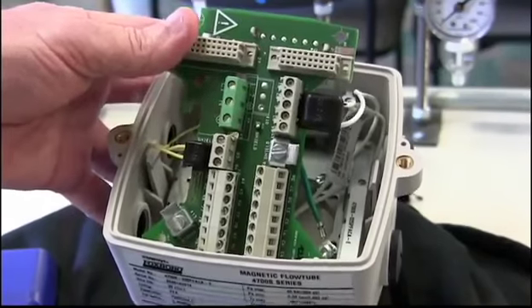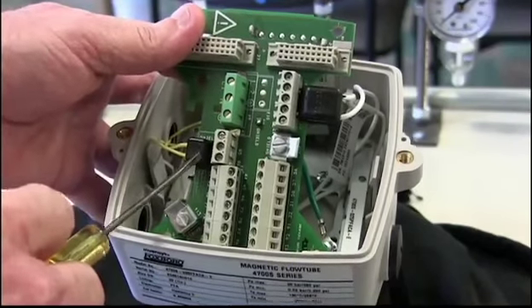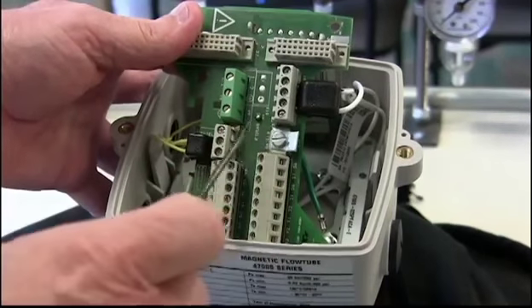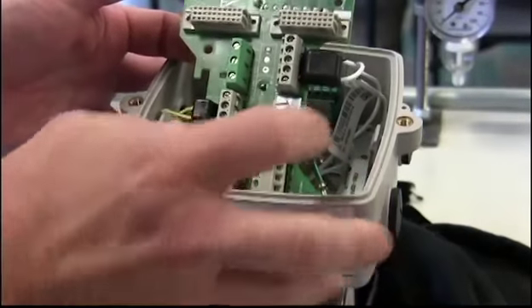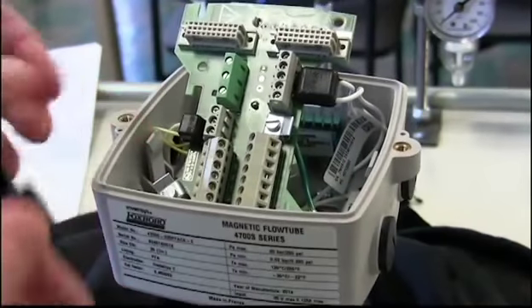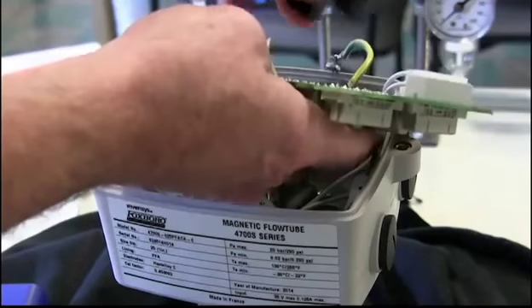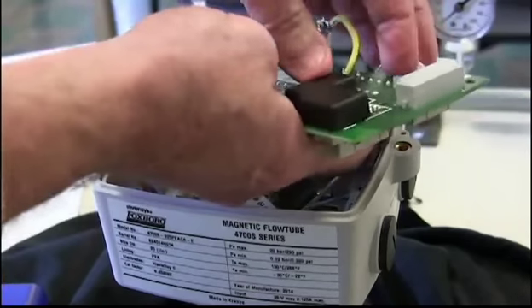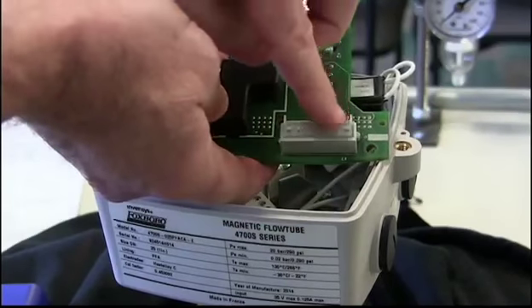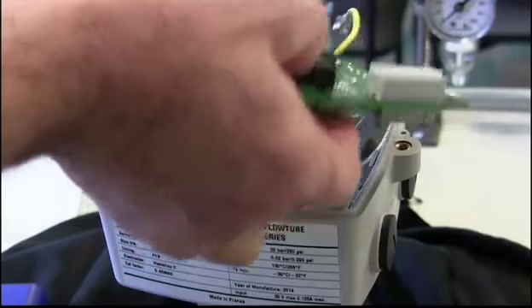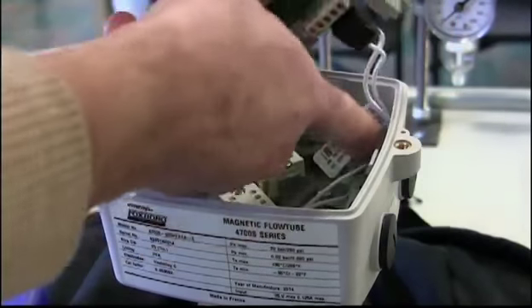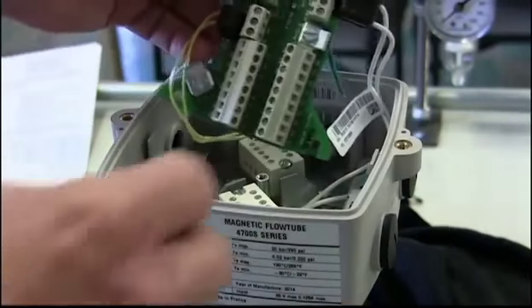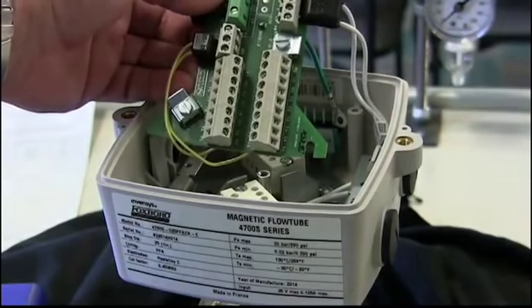Okay, now that I've added the coil terminal to the connector board and the signal connector to the board, now would be a good time to replace the shroud in the back of the connector board. So just flip it over a little bit and line this up, and it just snaps right back on there. Now at this point you will notice that the terminal for the connector for the sensor prom needs to be placed directly over the sensor prom in the transmitter, and simply push the connector assembly down straight on top of it, and when I come back it'll be done.